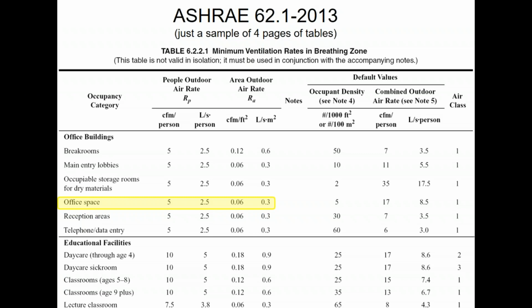The reason we do it that way is because when we get to demand ventilation, we have to be able to separate those two components. So from a code perspective, we have to tell you what the two components are instead of having them in a blended number. So you simply add them together, right? If I have a 100-person space, 100 times 5, that's 500 CFM. If I have 10,000 square feet, 10,000 times 0.06 is 600 CFM. 500 CFM plus 600 CFM means I have 1,100 CFM of outside air required, right?